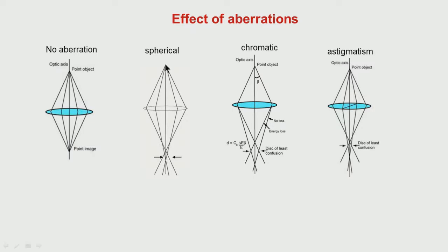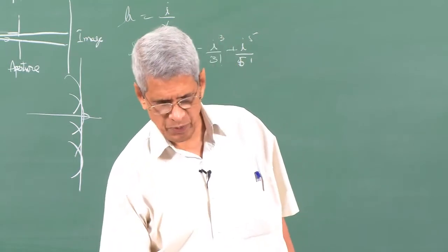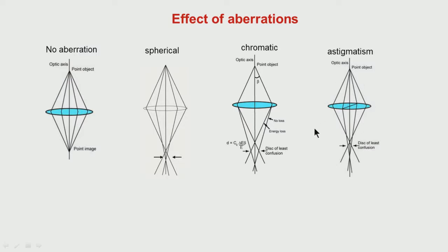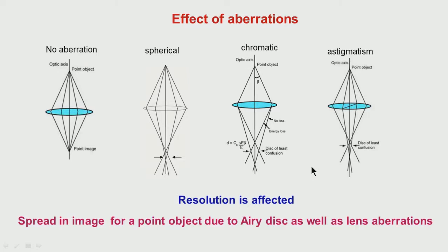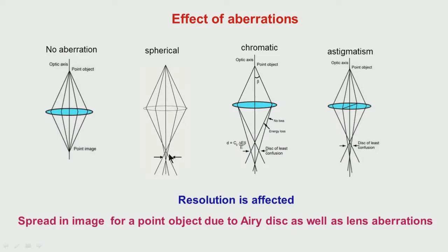Spherical aberration causes a point object to appear as a spread image. Chromatic aberration similarly spreads the image, but it has nothing to do with the lens geometry — it arises from the non-monochromaticity of the beam. Other lens defects include astigmatism, coma, and curvature of field. Because of aberrations, the resolution is worsened, and the total spread is the combination of the Rayleigh criterion spread and the spherical aberration contribution.